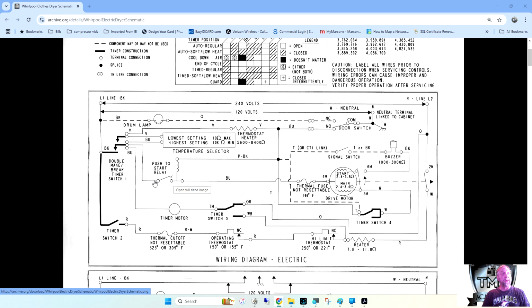Wow. So that power has to go through here to feed the motor. But if that switch opens, does the motor get power anymore? No. But when you close it and send power to the motor, power also goes through this coil right here and goes to neutral. That's a magnet that holds this switch closed. So now instead of a momentary switch like our GE, and I'll put them side by side so you can compare them.